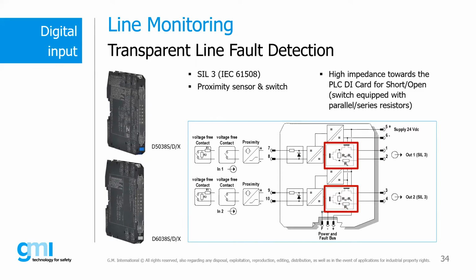On the other hand, when the contact in the field is in the closed condition, RH minus RL is short-circuited by the transistor in parallel with it, and the PLC will see an impedance of the value of RL. In the same way as before, the digital input card that applies a voltage to the loop will read a return current value equal to the closed state of the contact in the field.